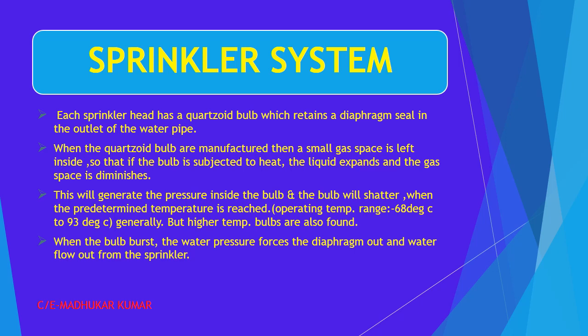When the quartzoid bulbs are manufactured, the liquid is filled in, and after that a small gap in which the gas space is left, so that the bulb can be subjected to heat. When it is subjected to heat, the liquid will expand and the gas space diminishes. Due to the heat the liquid expands and the gas is pressurized, and then the bulb will shatter. This generates a pressure inside the bulb, and the bulb will shatter when the predetermined temperature is reached.